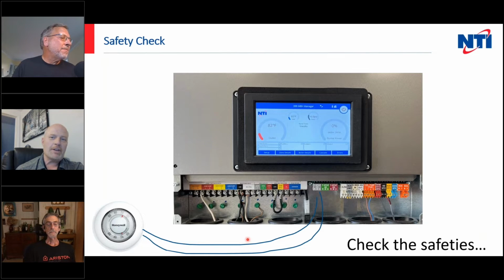So we've got our call for heat coming to the boiler. What I recommend, I'm a big fan of jumper wires. In a lot of cases, when I'm troubleshooting with you guys on the phone, I'll tell you to take the thermostat off and just use a jumper wire, because I know exactly what that does when you're using it. Not always sure what the thermostats are doing.